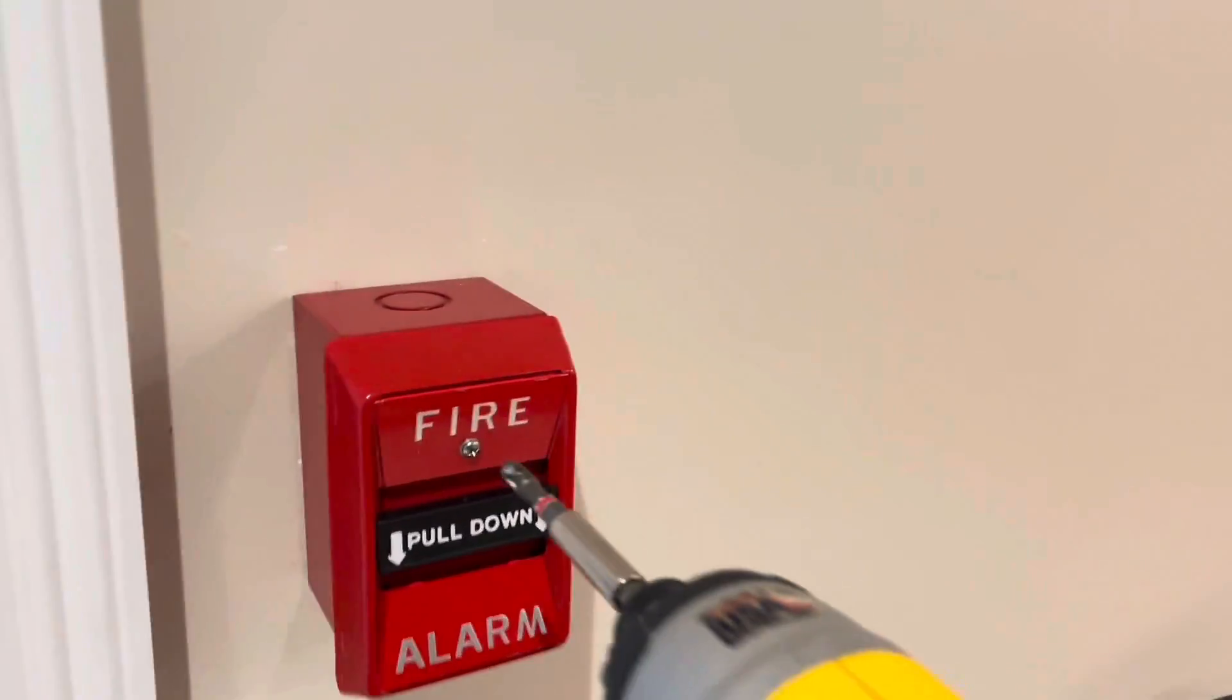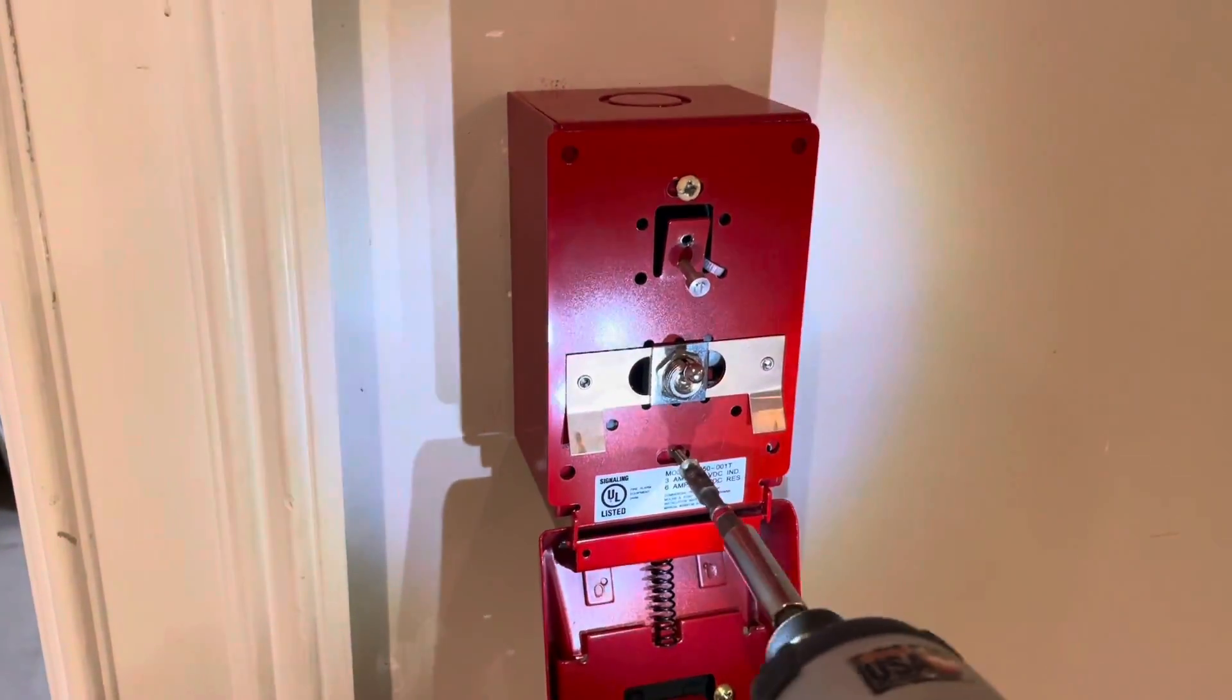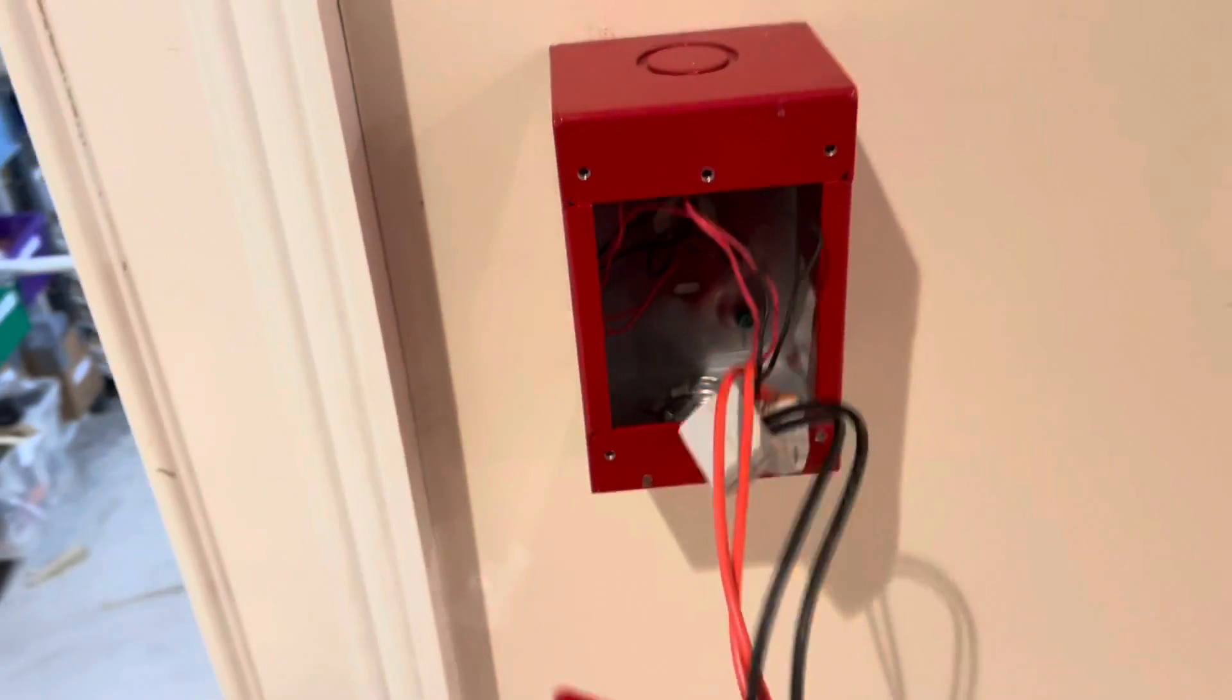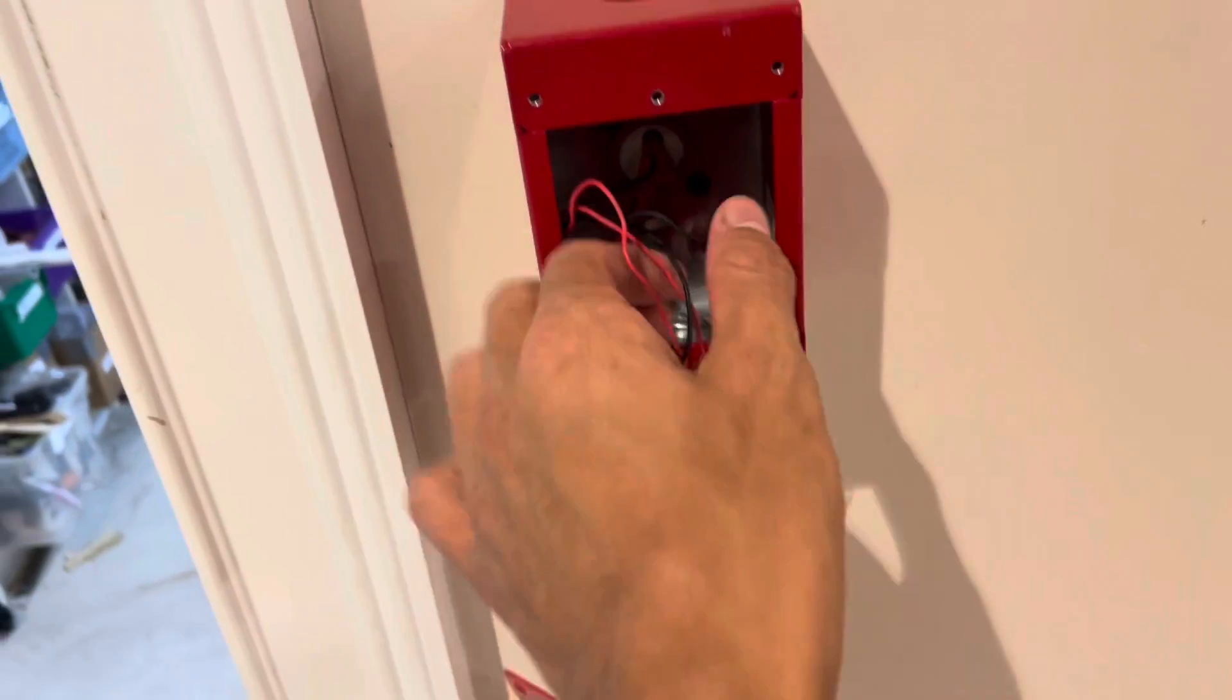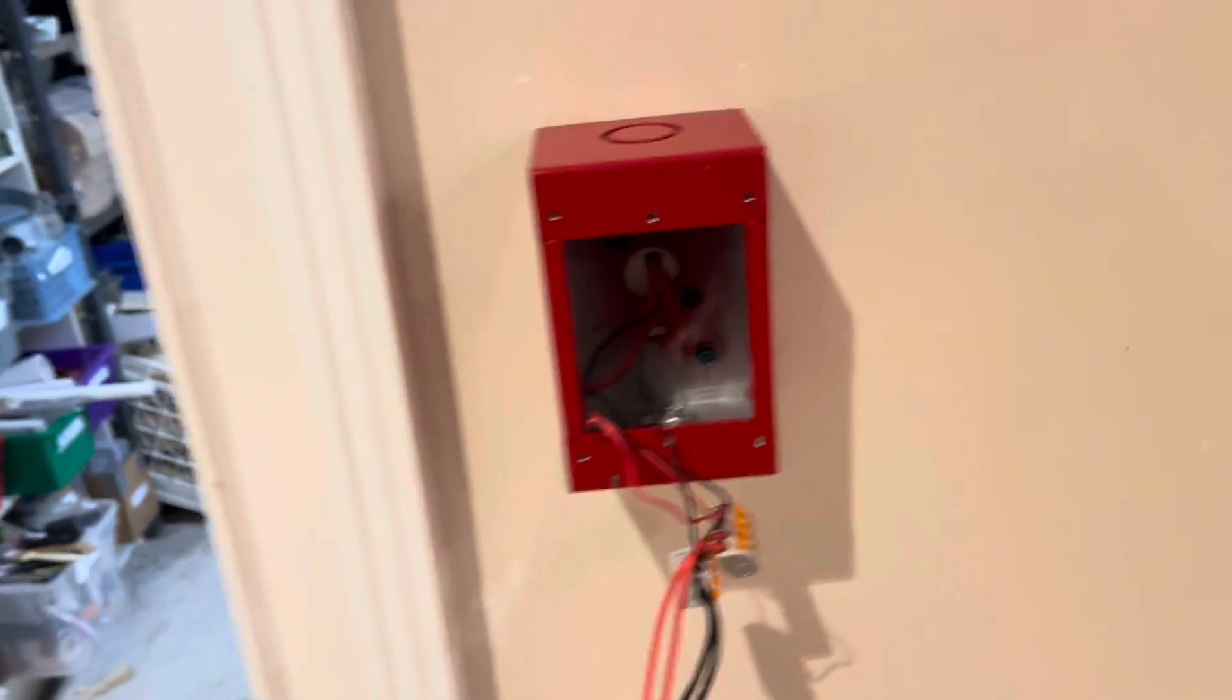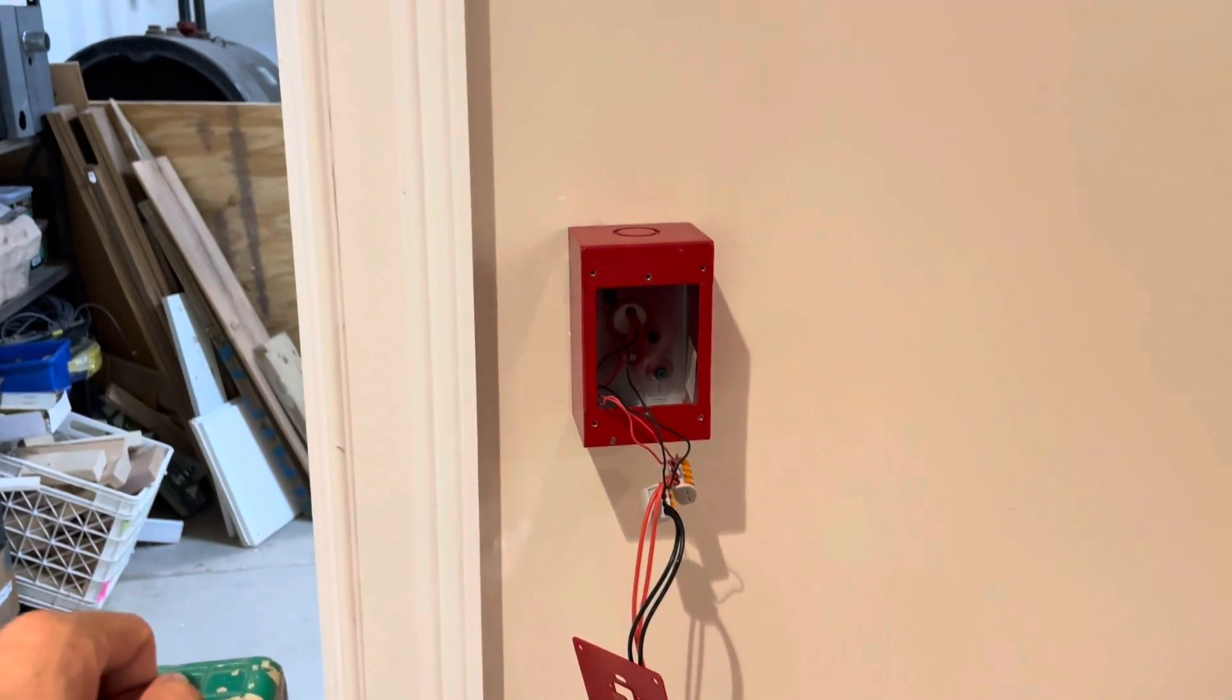Let's start removing the pull station so I'll just undo the screw right here. Once again this pull station is wired with Wagos so all I have to do is remove those tabs. Also I'm going to be installing a simplex specific back box just because it looks better. In this case obviously this box would fit any simplex pull station but just for the sake of appearance.